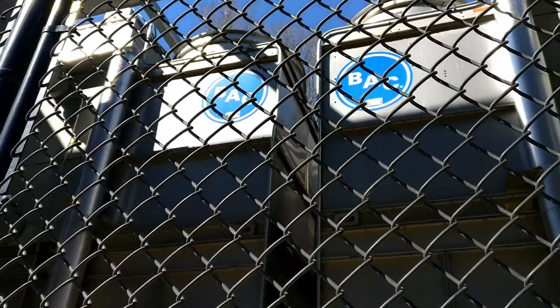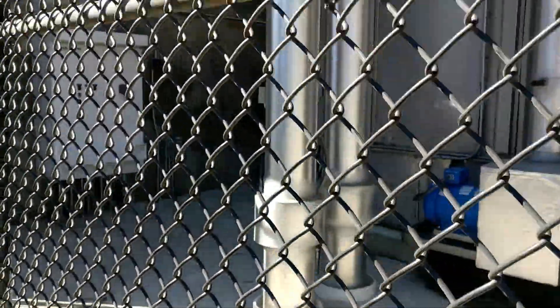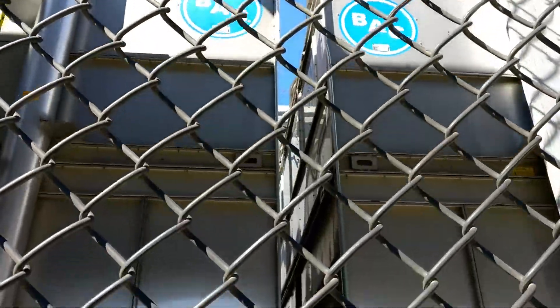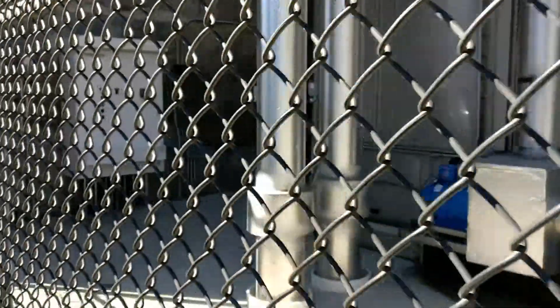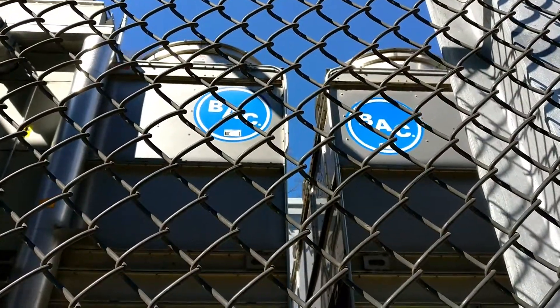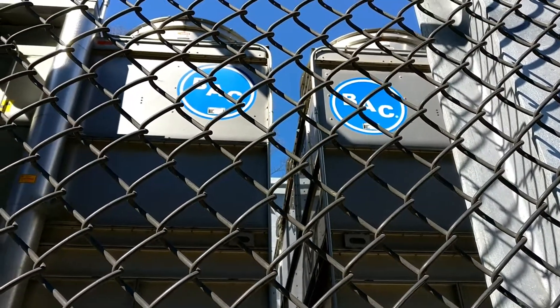These are the closed circuit towers for the water loop. They're off right now because it's about 35 degrees outside in early March. Each one has a control panel, and everything is enabled and disabled by the energy management system. They'll be running these pretty soon with spring coming up. Two of them serve the loop.